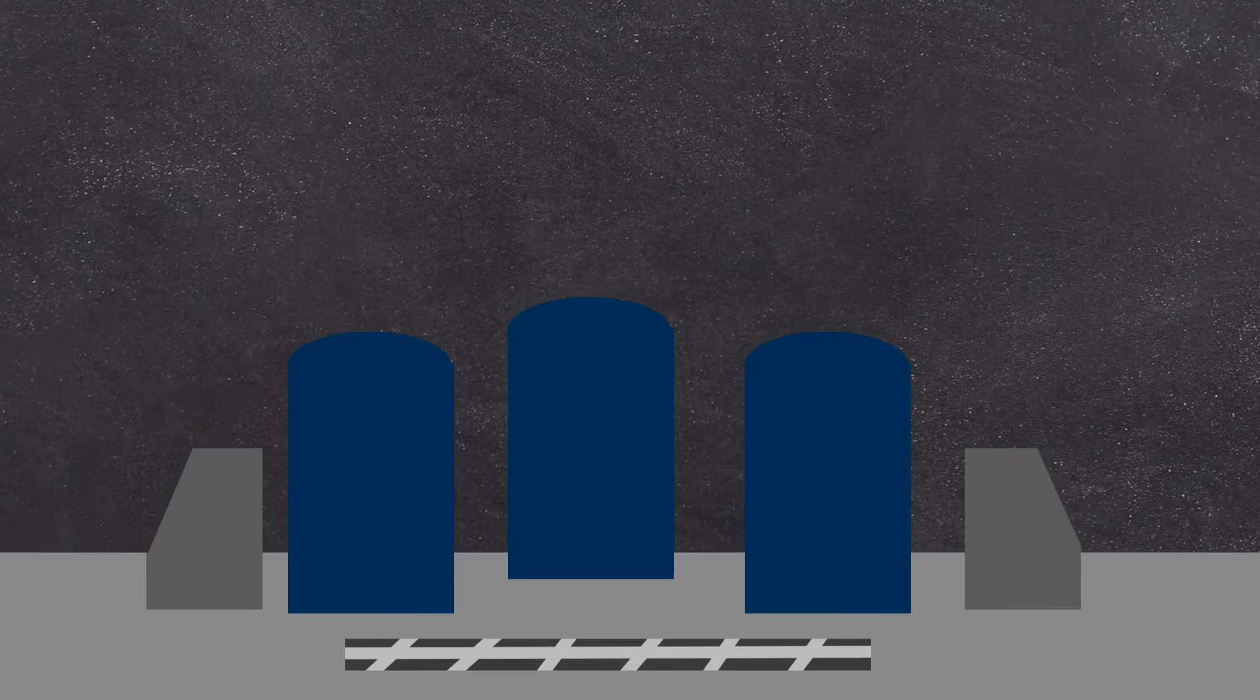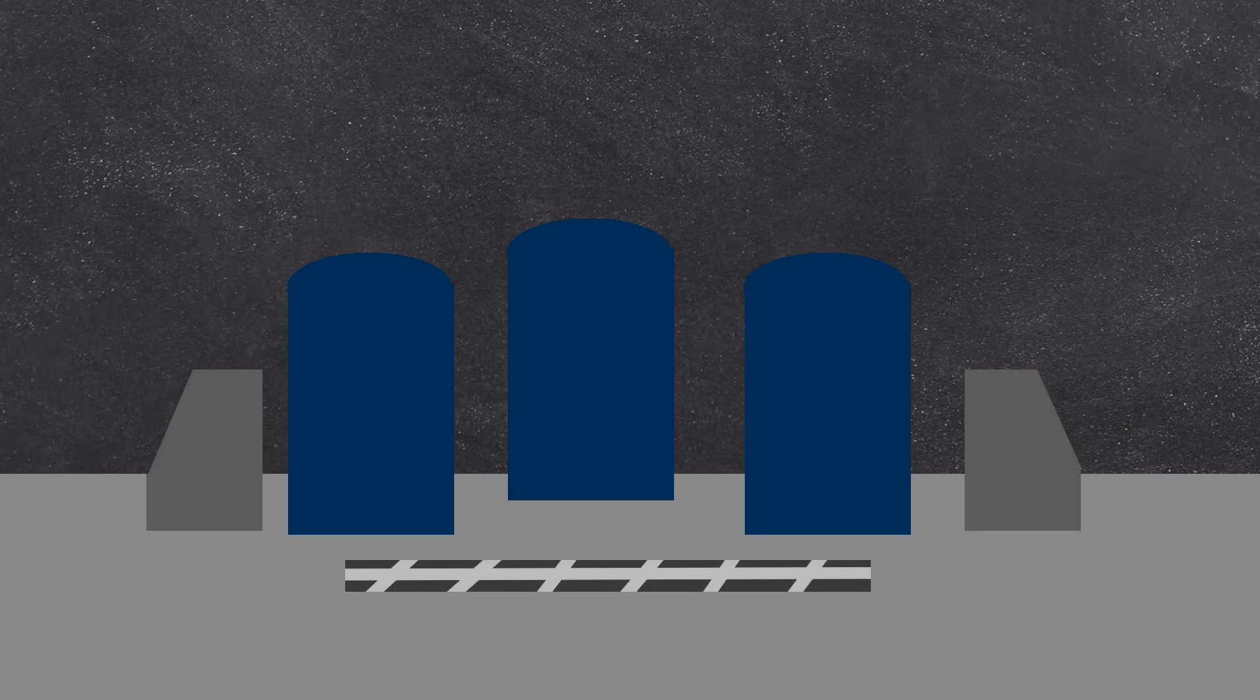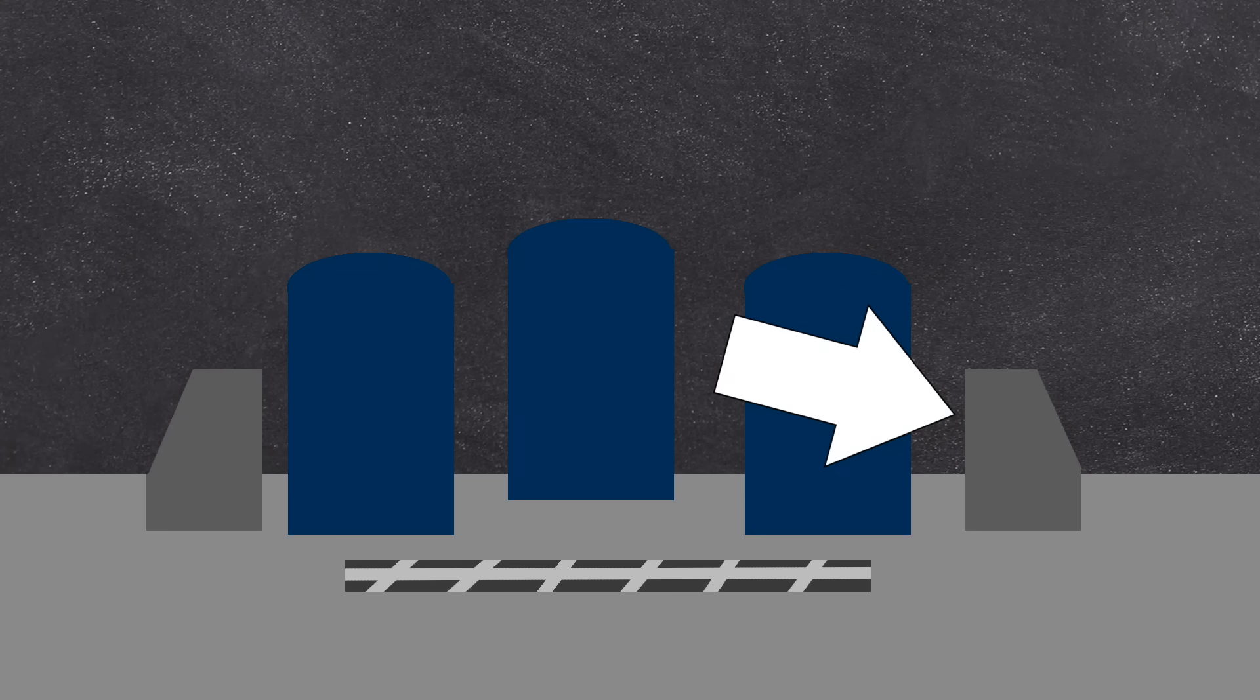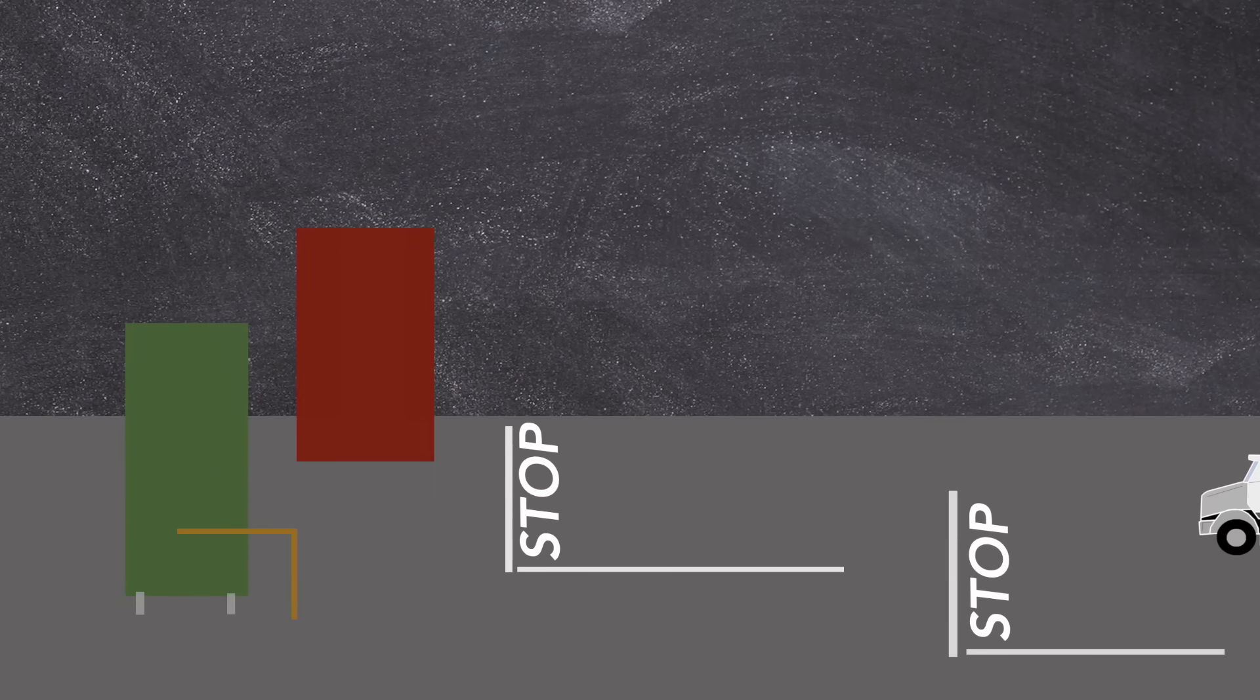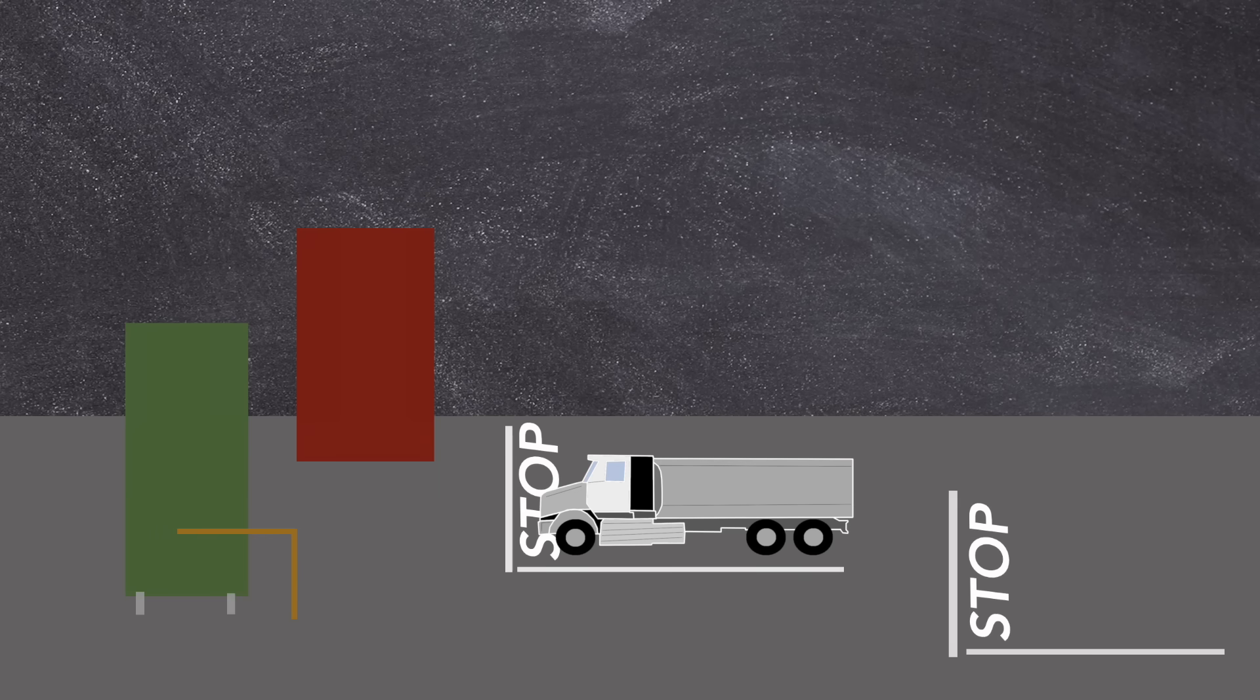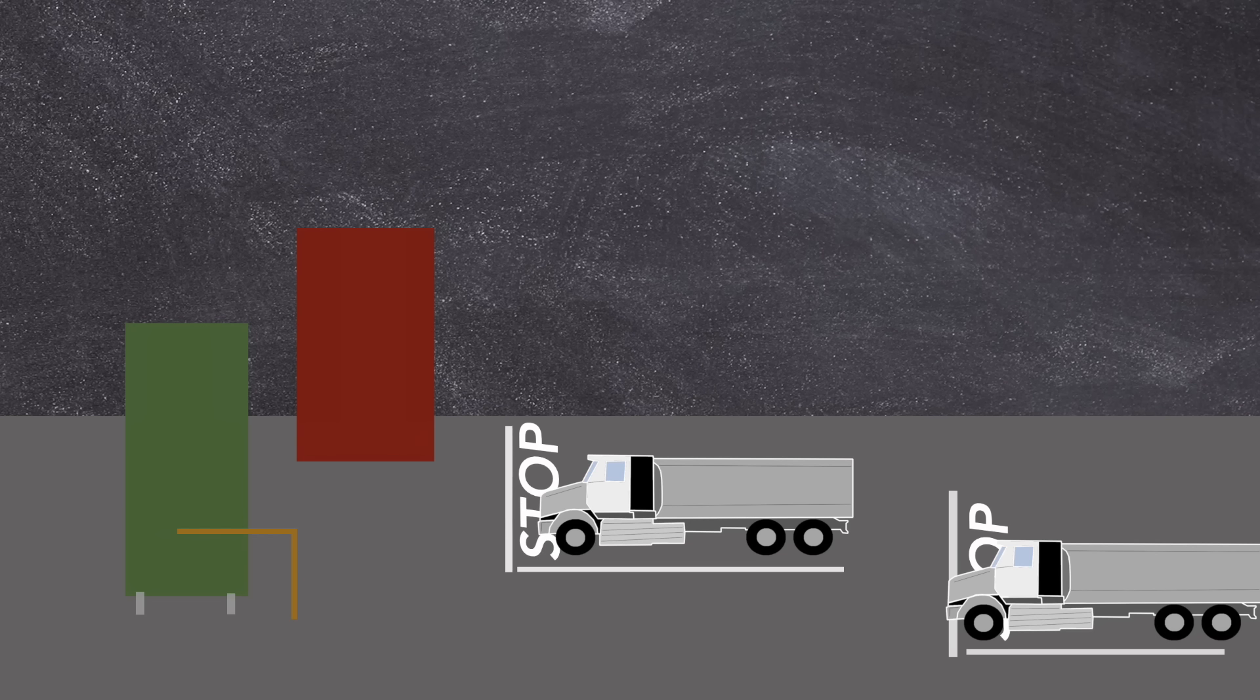Vast amounts of fuel was pumped and stored on site from dedicated tank farms. The tanks themselves formed the primary containment of hydrocarbons. If there was a leak, then there was a secondary containment in the form of retaining wall bunds provided. If all that failed, there was tertiary containment. This was in the form of drainage and catchment areas. The secondary and tertiary forms of containment were focused on limiting environmental contamination.